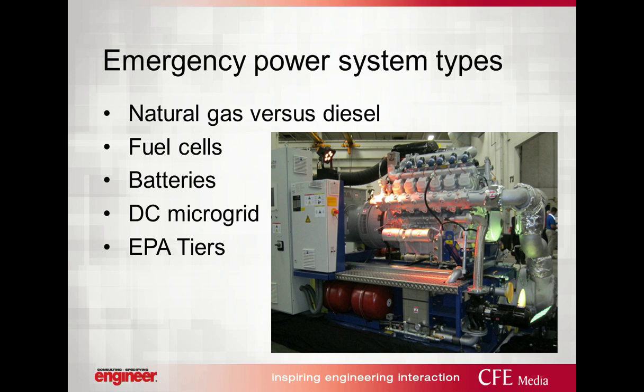So now we get to the types of emergency power systems, or as NFPA 110 calls them, EPS. Now, we do have options. While we typically see generator sets being used, and a lot of our examples are generator sets, code does allow for fuel cells or batteries or DC microgrids. Regardless of the makeup, code defines the requirements for time transfer and run duration, and we'll discuss a little bit about that later. The most popular question is the use of natural gas for emergency standby.